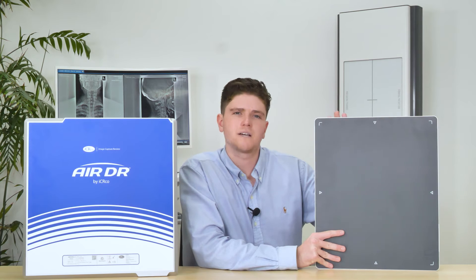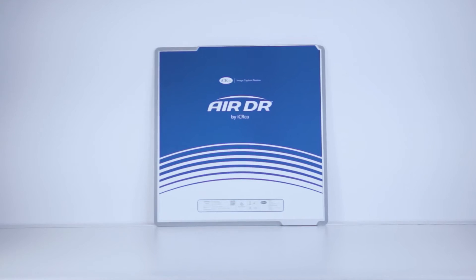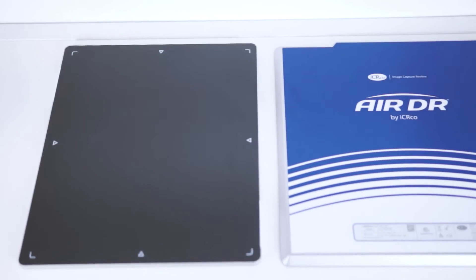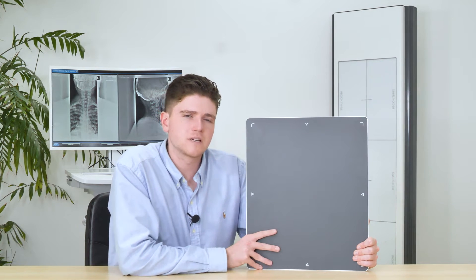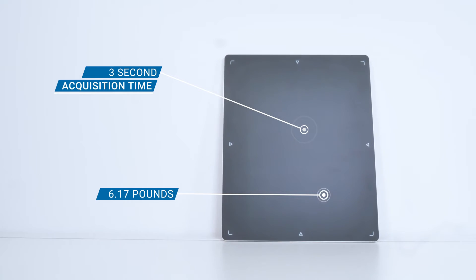The AirDRP is our 14 by 17 wireless panel, whereas the AirDRCP is our 17 by 17 tethered panel. Each panel comes with the options of either cesium or Gadox scintillators. Our wireless AirDRP comes with a 3 second acquisition time and is extremely lightweight, weighing just over 6 pounds.